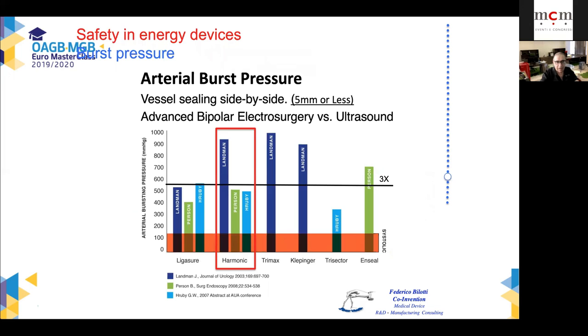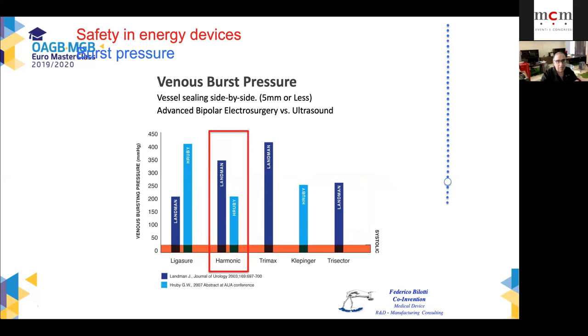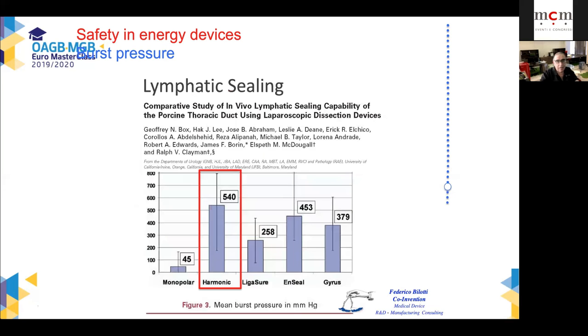These are some publications that describe how much the ultrasound device is capable of resisting arterial burst pressure, thanks to its inability to bring electricity, which damages the walls of the artery. But the sticky coagulum transforms the tissue of the arterial wall in such a way that these are incredibly strong, as a new tissue is created. It's not two walls that are glued together or stuck together as the electricity forces them to do, but it's a way of tissue to be transformed. These are the venous burst pressure. These are the lymphatic sealing mode, always stronger in resisting internal pressure.